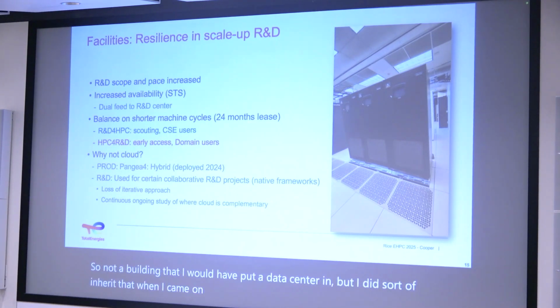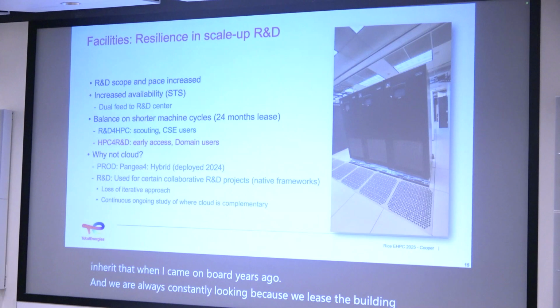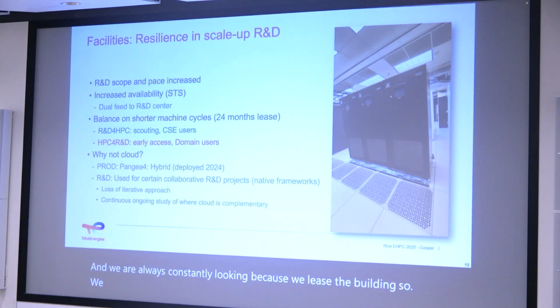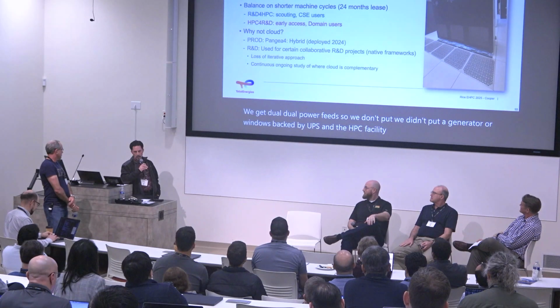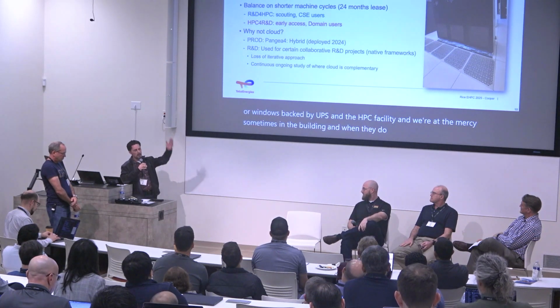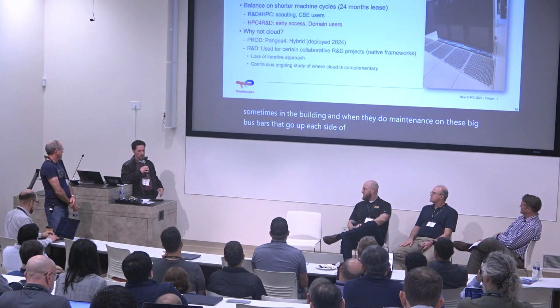Since we lease the building, we get dual power feeds instead of a generator—we're just backed by UPS in the HPC facility, and we're sometimes at the mercy of the building. When they do maintenance on the big bus bars going up each side of the high-rise—these 4,000 amp buses that are tenant power—there's barely any breaker space left; we've stuck breakers just about everywhere possible. They did make buildings very capable in the 70s though. We've got several megawatts of computer power in a building that was overbuilt for back then.